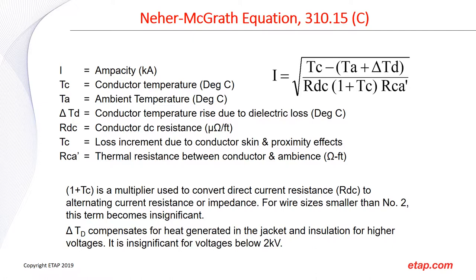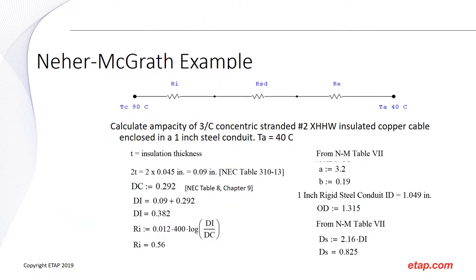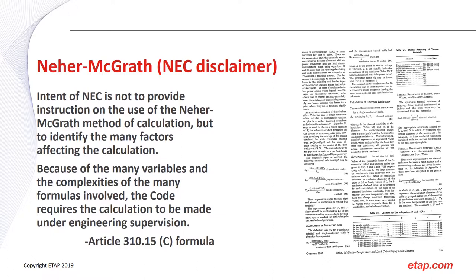The Neher-McGrath equation is provided in NEC Article 310.15. The NEC doesn't really provide guidance on how to use it but includes this disclaimer: the intent of the NEC is not to provide instructions on the use of the Neher-McGrath method but to identify the many factors affecting the calculations. Because of the many variables and the complexities of the formulas, the code requires the calculations to be made under engineering supervision. The NEC also doesn't provide the actual Neher-McGrath paper — only the generalized equation.